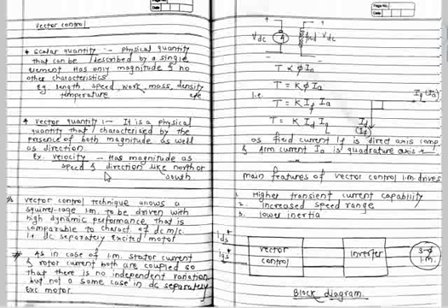So the most suitable is obviously vector control, because in case of vector control, there is field oriented control. It gives more accurate control of AC motors as compared to the scalar control. So they are used in drive applications where oscillations in air gap flux linkage are intolerable, that is in case of robotic applications, centrifuges, servos, etc.